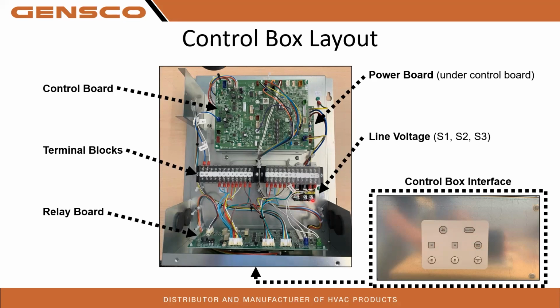Right here, you have your line 1 or your line voltage coming from the unit, from the heat pump, along with your communication. So your standard 14/3, S1, S2, S3 is going to connect right here and go to your heat pump. Behind this control board is the power board for this thing. Not much you really need to do on that thing. They put it in a nice, real easily accessible spot back there. Not really, but it's back there. Like I said, not much you're going to need to do with that.